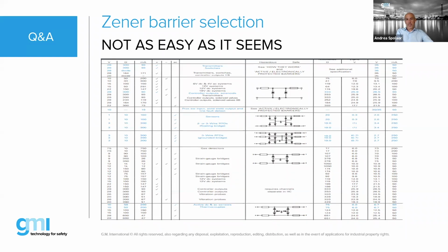It's not really easy, but we would say that isolator barriers are more standardized. You can have isolator barriers that are mostly universal for all temperature sensors, for all milliamps or voltage, so it's easy for people using isolated barriers. There are some applications where you have to check if you're using encoders, antennas, and so on. But basically, isolated barriers are the simplest way to use. They come in so many varieties that can be selected for any application.